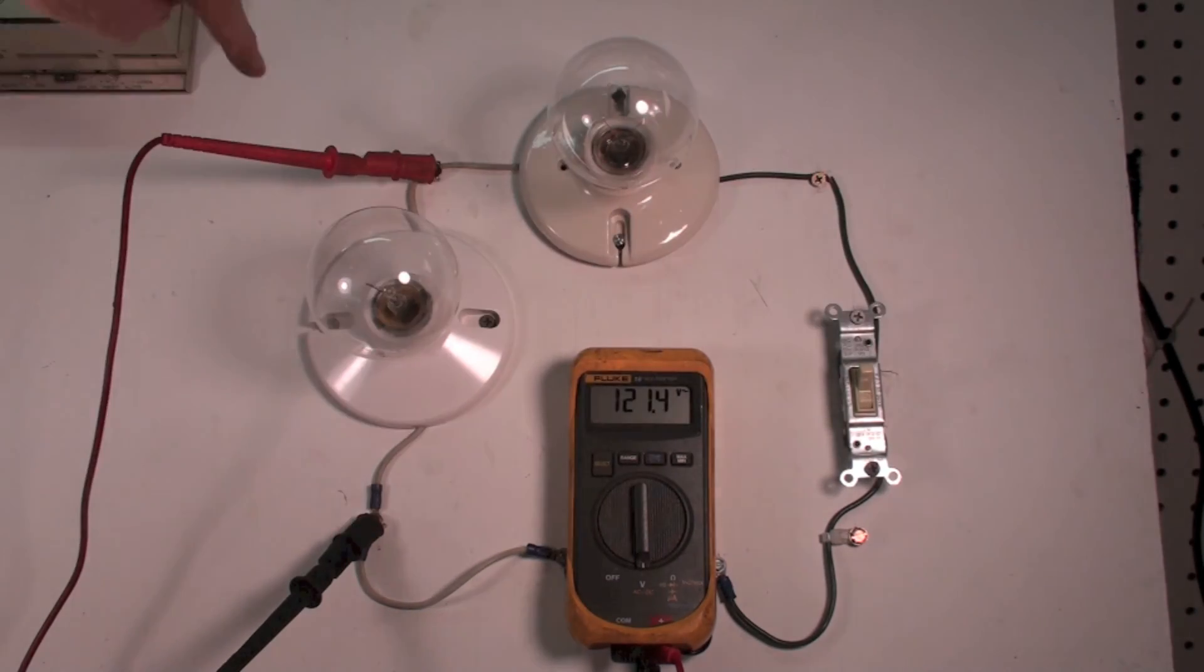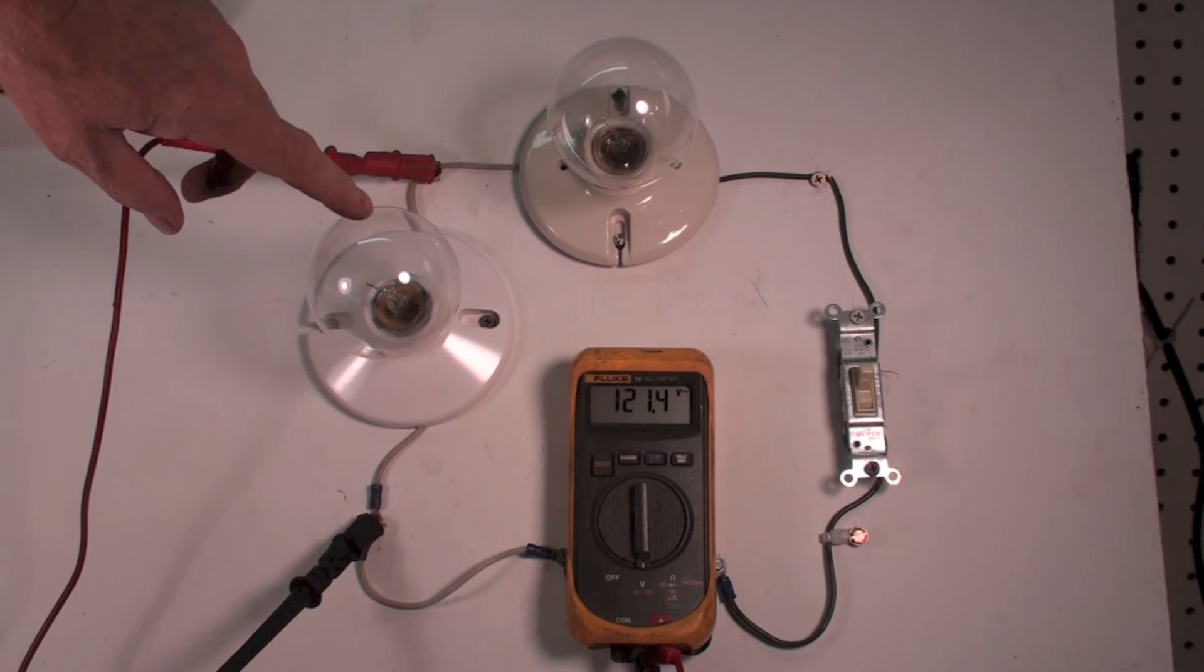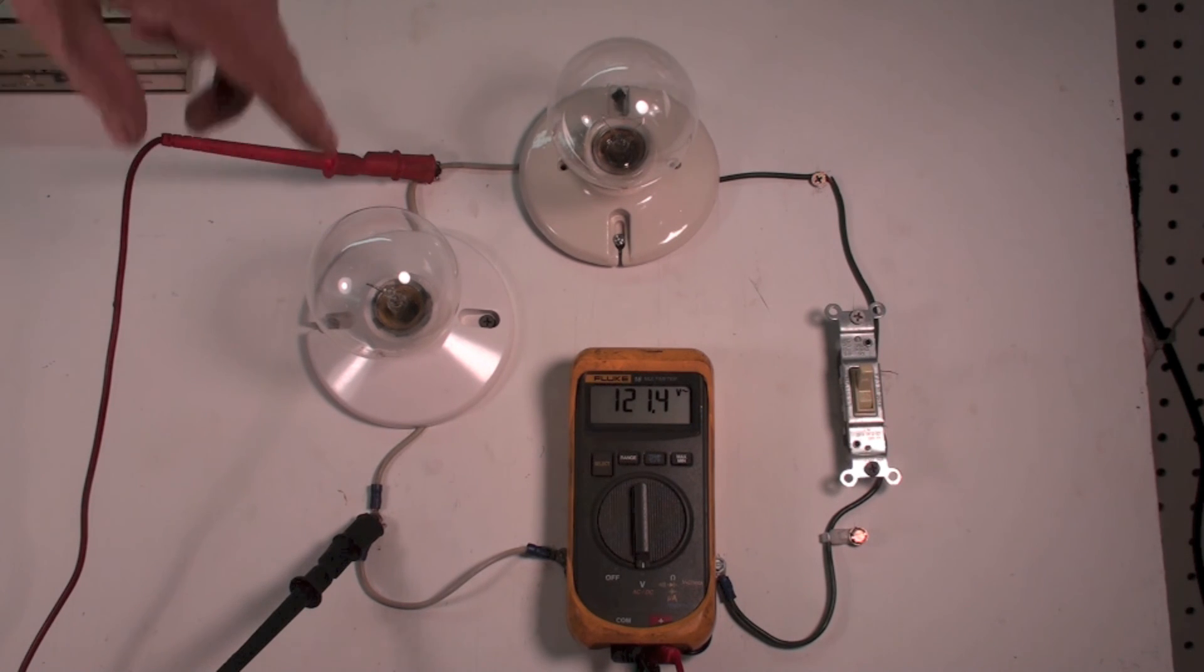I'm reading a complete circuit because I got a circuit that's good all the way through except here. Remember when I did this before, if I read 121 volts across the load and the load wasn't working, then my load had failed.